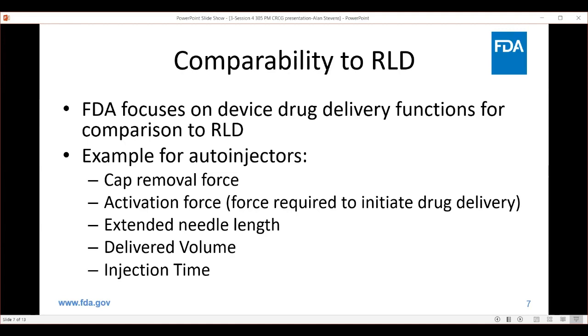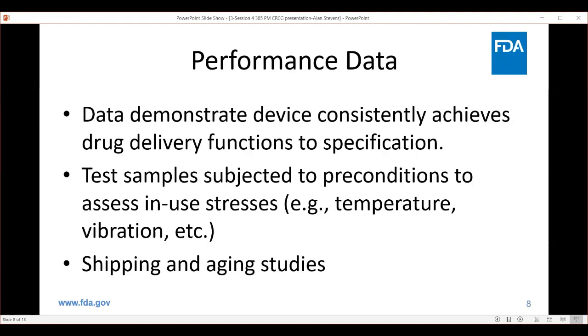And then from there, we're looking at: do you consistently and reliably meet those specifications, for example, per the ISO standard? So it's two sets of questions. One, do you have the right specifications? And then do you consistently meet them? And that's what I'm going to talk about now in terms of the actual performance data that we're looking at. So given the specifications that you have, say for activation force, are you meeting that performance consistently? For injectors, the ISO 11608 standard is the primary method that we use for design verification of these devices, as an example. And that standard provides a lot of robust test criteria, preconditioning, and endpoints.